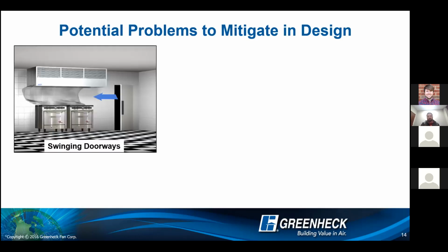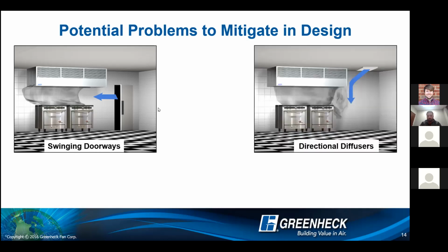The first one, and probably the most common one, is swinging doorways or high traffic areas near the hood. You can't necessarily change that, a doorway is going to be where the doorway is going to be, or a serving area is going to be where it's going to be. So you're going to have high traffic areas, but it's important for you to know where those high traffic areas are so that you know if you need to increase your CFM, or if you need to provide end panels or end skirts to these hoods in order to mitigate these. But swinging doorways and high traffic areas, you should be on alert for.